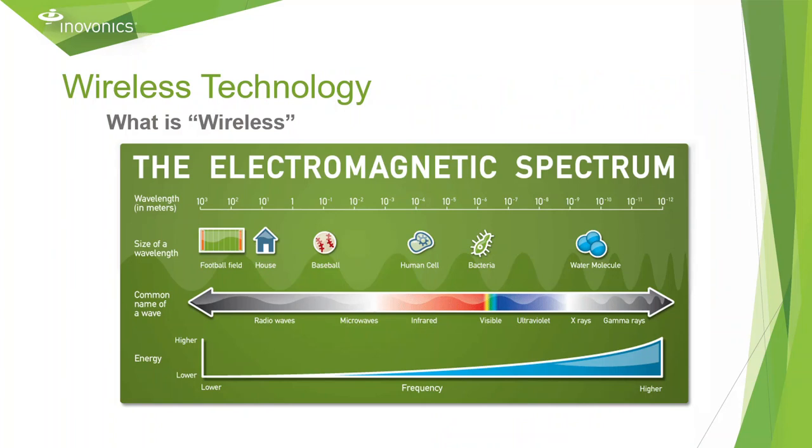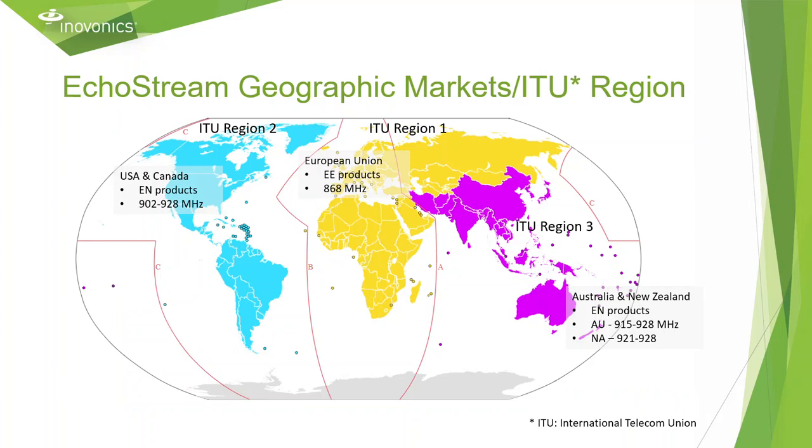Inovonics wireless devices operate between 868 and 928 MHz depending on your region. This range all operates within that red box on the electromagnetic spectrum. The only difference between all of these radio waves within that box are frequency and wavelength, which plays a large factor in how they operate in different environments. This spectrum is subject to change based on the region. In the United States and Canada, we operate from 902 to 928 MHz. In the European Union, we operate at 868 MHz. In Australia and New Zealand, we operate within 915 and 928 MHz.